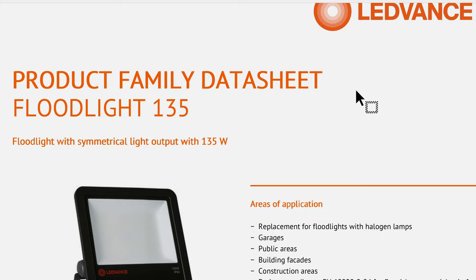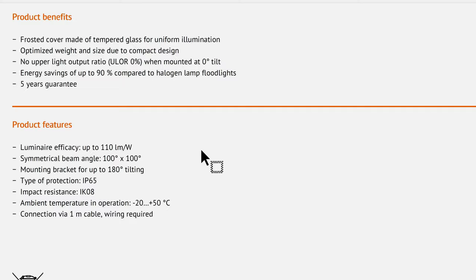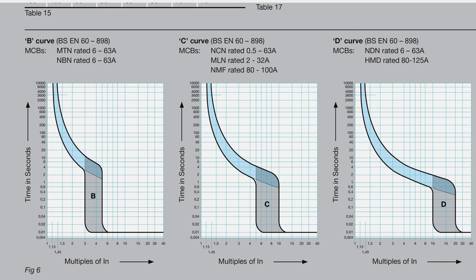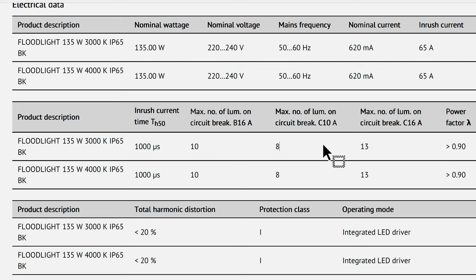This particular datasheet from Ledvance for a 135-watt floodlight actually states the maximum number of floodlights on a circuit breaker. It says maximum number of luminaires on a circuit breaker with a B curve at 16 amps is 10, and for a 10-amp circuit breaker following the C curve, we can only have eight. If you calculate eight times 135 watts that's 1080 watts, but a 10-amp breaker at 230 volts is 2.3 kilowatts — showing you can't just divide rated current by nominal floodlight current.